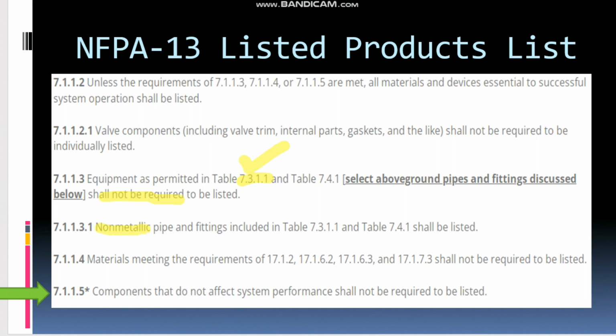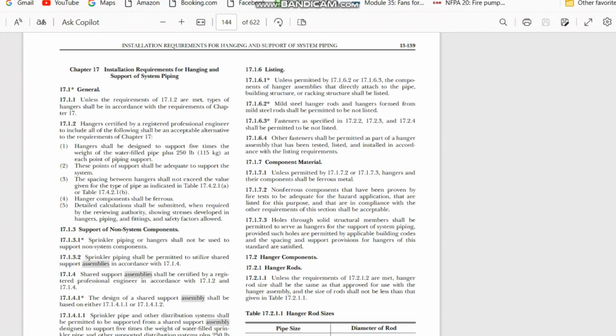But non-metallic pipes and fittings included in the table shall be listed. Even though it is there in Table 7.3.1.1, non-metallic means CPVC pipes like this, even though it is there in the table, it has to be listed. Then material meeting the requirements of this shall not be required to be listed. I'll show you what this is. One of the important points here, if you see 17.1.6.2, is that mild steel hanger rods and hangers formed from mild steel rods shall be permitted to be not listed.